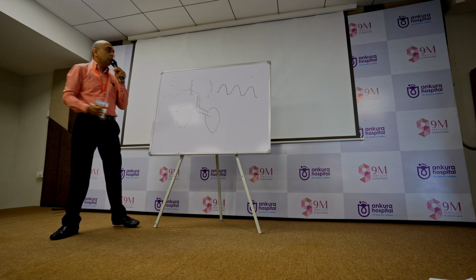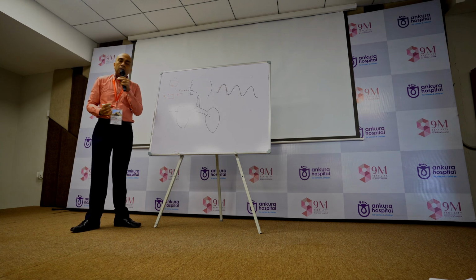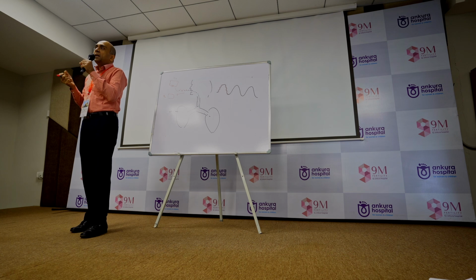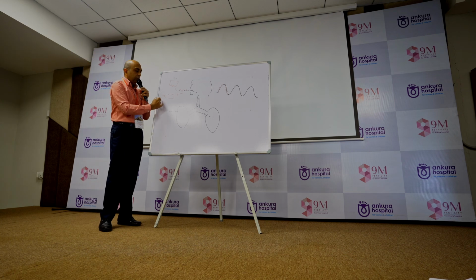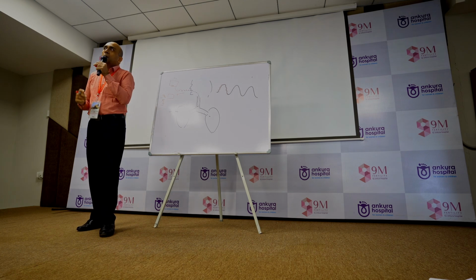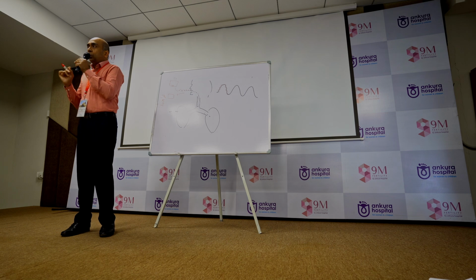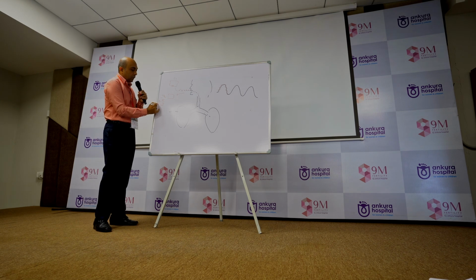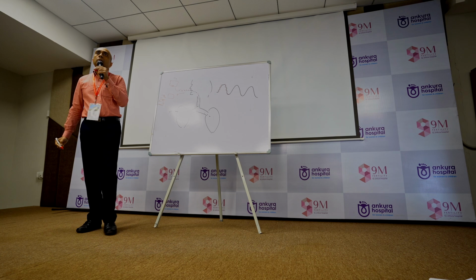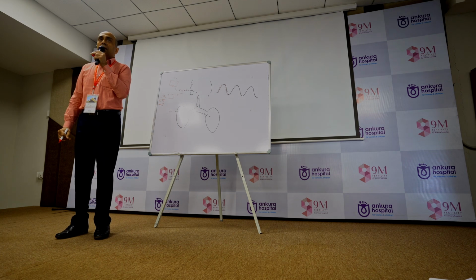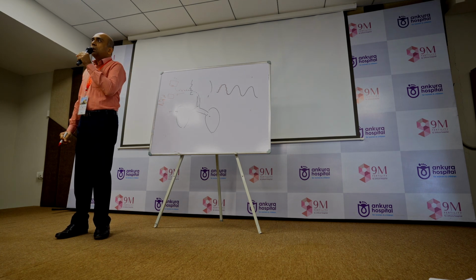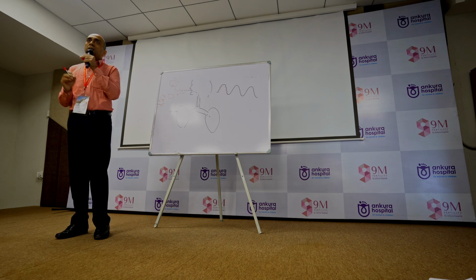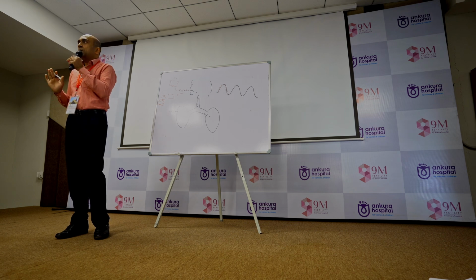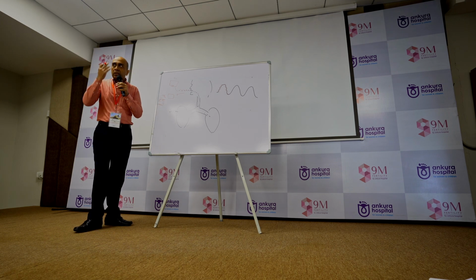So directly, whatever changes are happening from inspiration to expiration, these transducers are picking them up. And they are directly measuring the pressure and the flow, because there are two transducers, pressure and flow. Pressure transducer and flow transducer. Okay? Later on, by Ohm's law, resistance is equal to pressure divided by flow. So by using Ohm's law, the machine calculates resistance, and that is pressure divided by flow. So pressure and flow are direct measurements. Resistance is the calculated or derived measurement. Am I clear here? Correct? So this machine will give you the resistance value, that what is happening in the resistance.